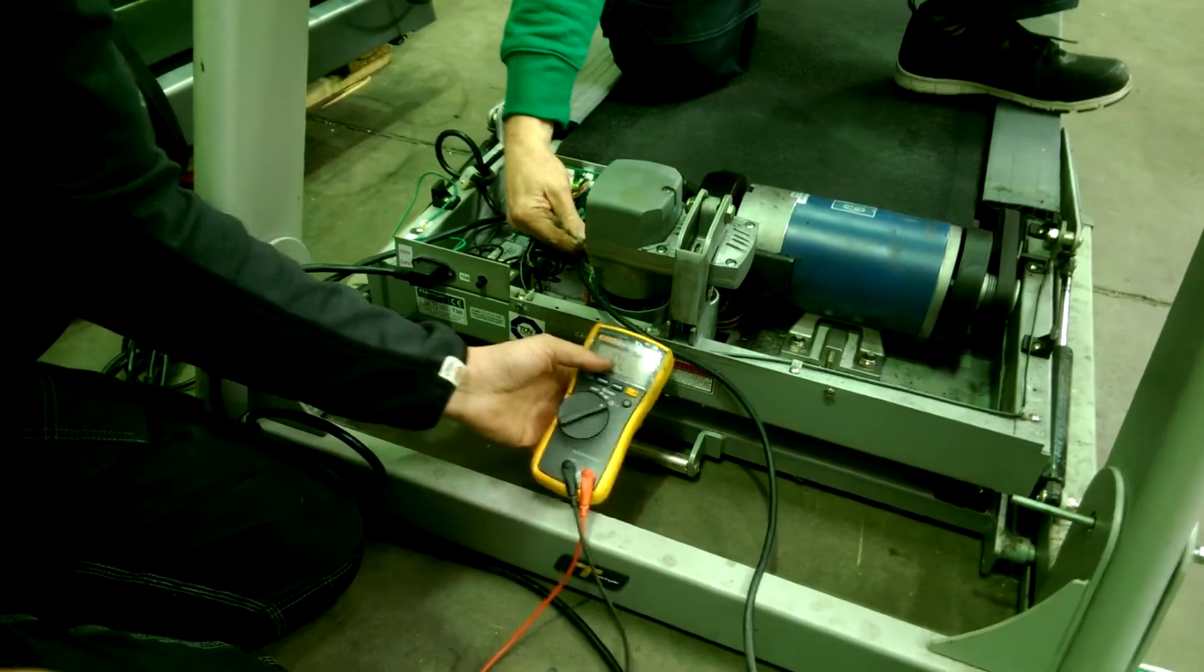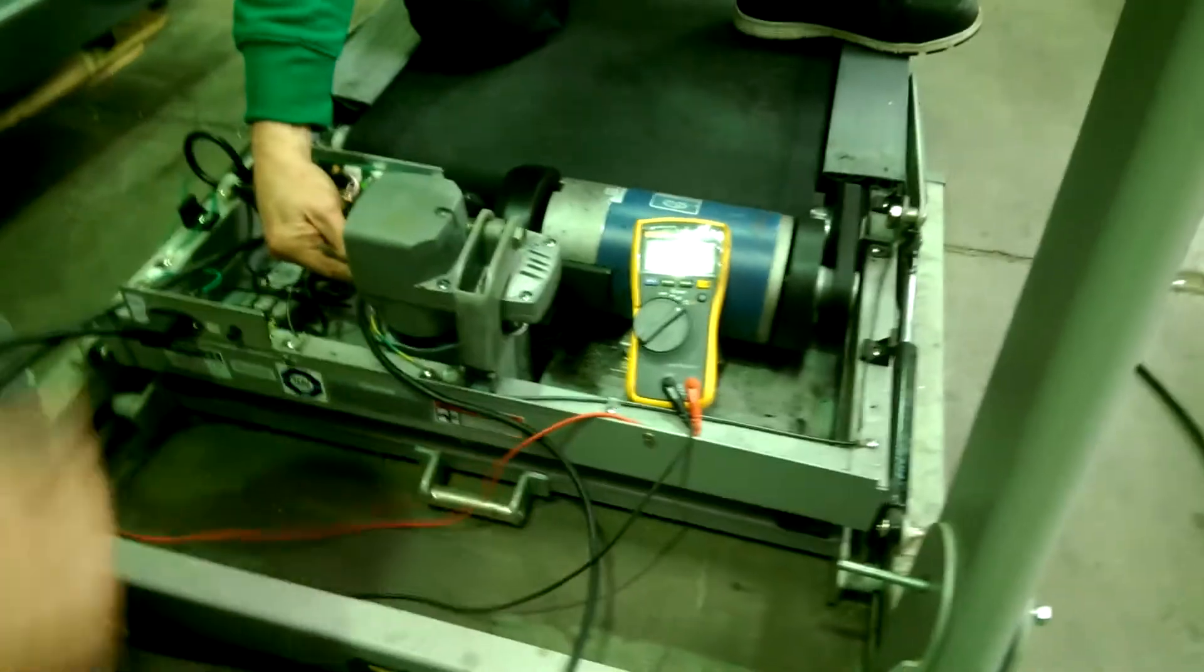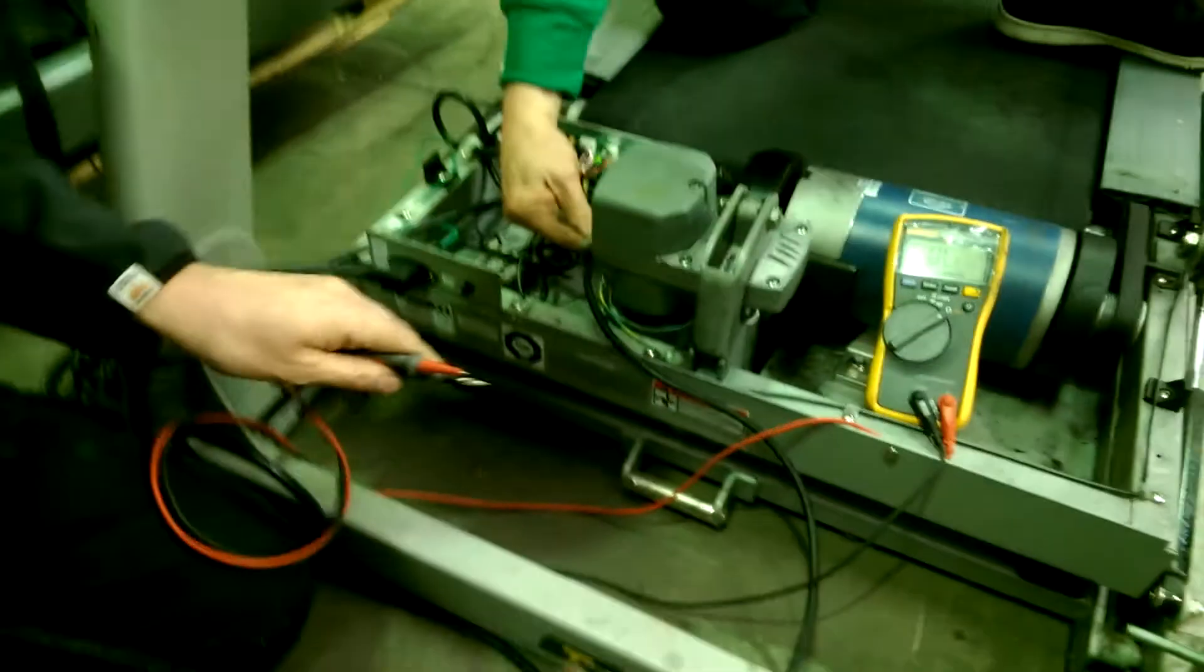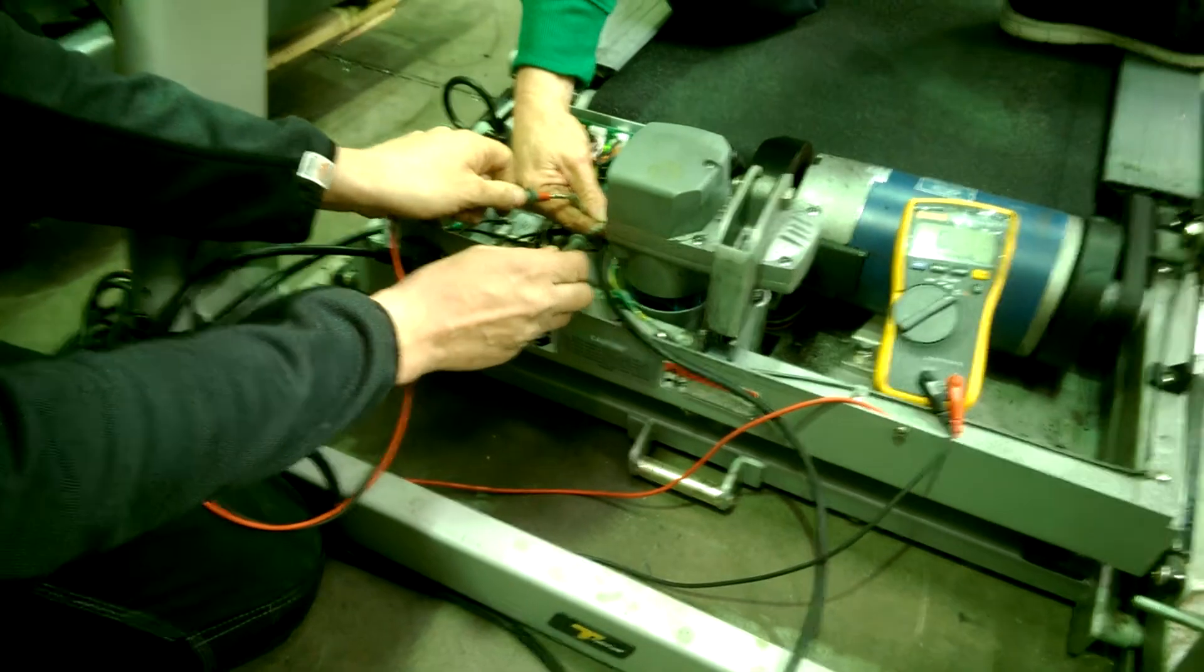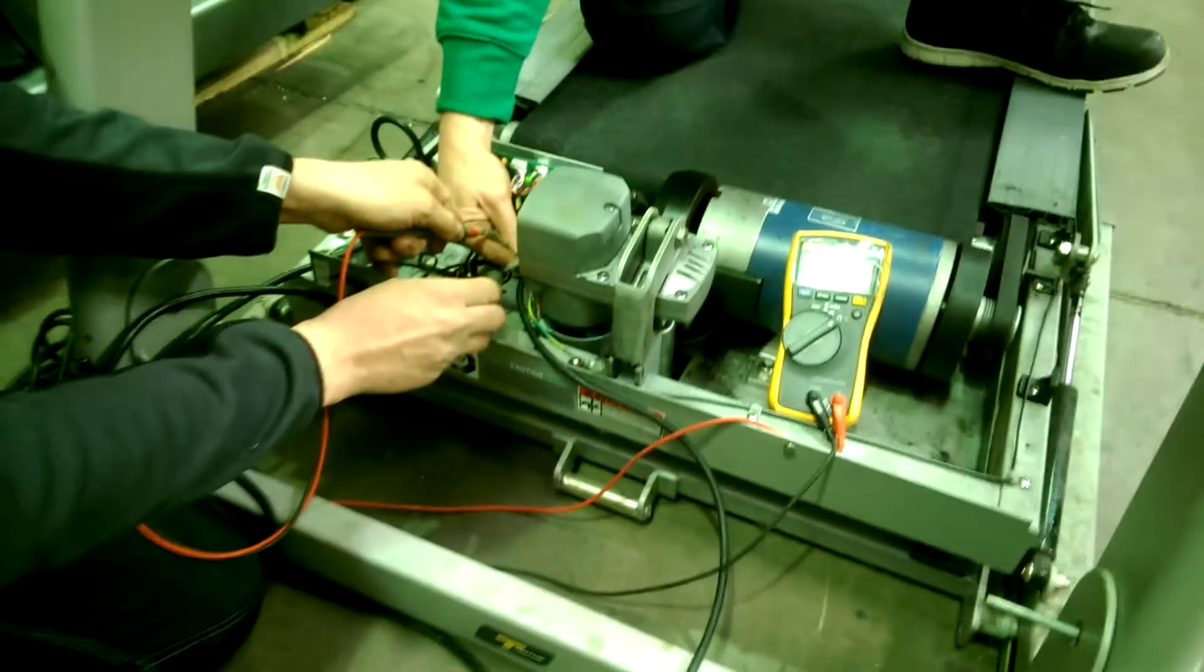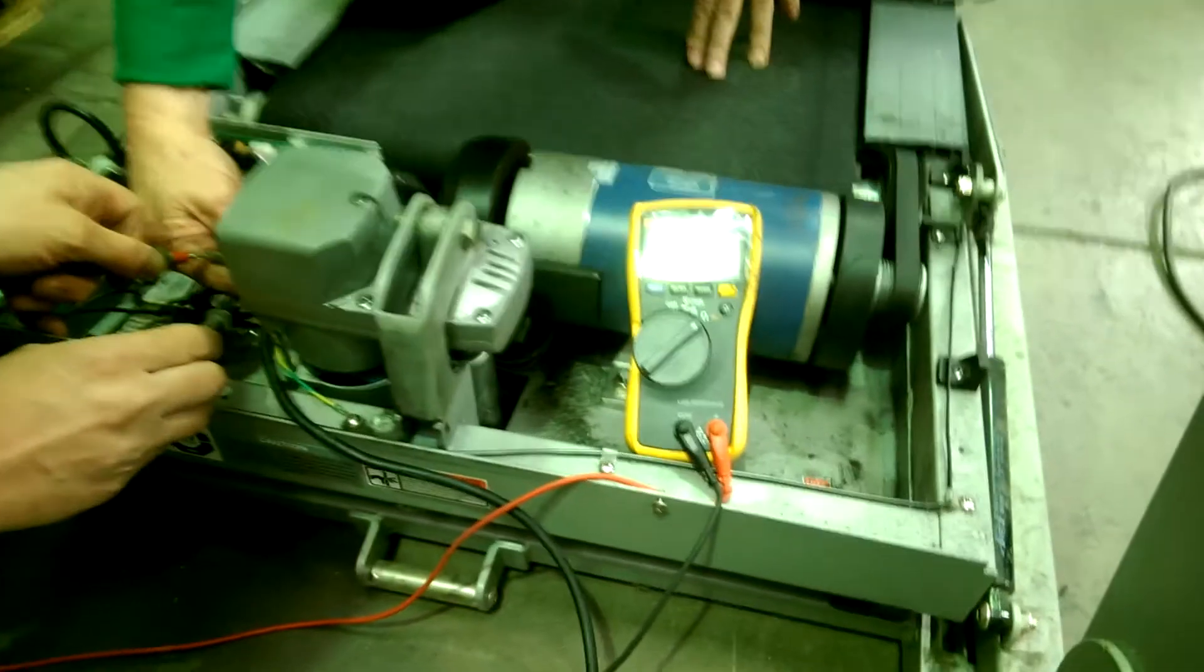We're going to measure what's going on with the motor. So these are the motor wires here and first of all, we'll measure the resistance of the windings, which is on this particular one 1.92 ohms, which is perfectly fine.